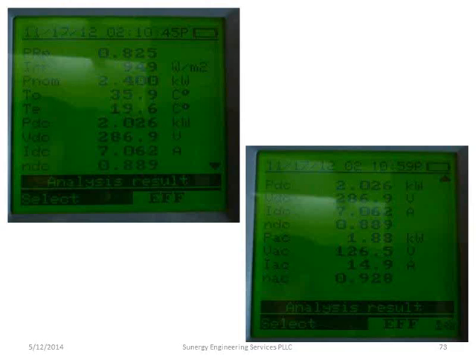It wants to do more, right? It's a 2400 watt array, so it would probably do pretty close to 2400 watts under these conditions. It's got full sun, a little warm, so it's probably a bit low because of that. But because this inverter can only process 1800 watts, it's cutting back, throttling the current, which forces the module off its optimum point. That's why it has lower efficiency than if it were at the knee of the curve, since the inverter is purposely dropping the current and drawing down the array current.